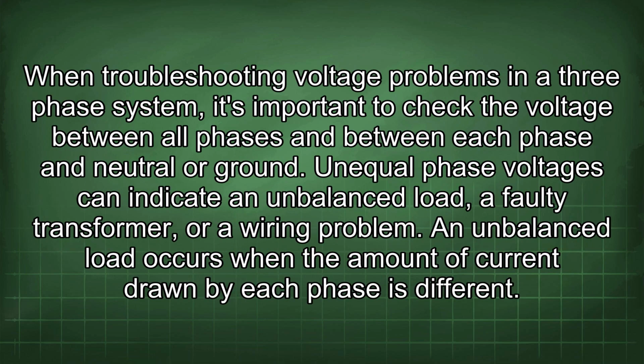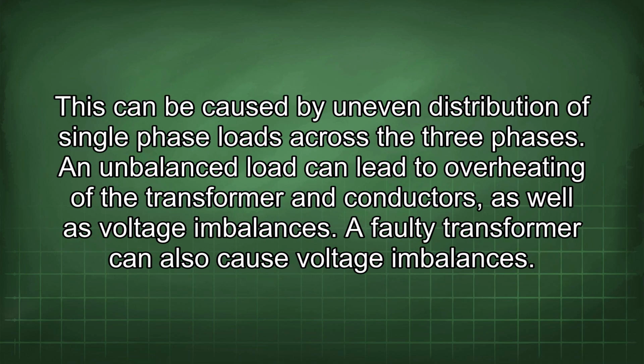When troubleshooting voltage problems in a three-phase system, it's important to check the voltage between all phases and between each phase and neutral or ground. Unequal phase voltages can indicate an unbalanced load, a faulty transformer, or a wiring problem. An unbalanced load occurs when the amount of current drawn by each phase is different. This can be caused by uneven distribution of single-phase loads across the three phases. An unbalanced load can lead to overheating of the transformer and conductors, as well as voltage imbalances. A faulty transformer can also cause voltage imbalances.